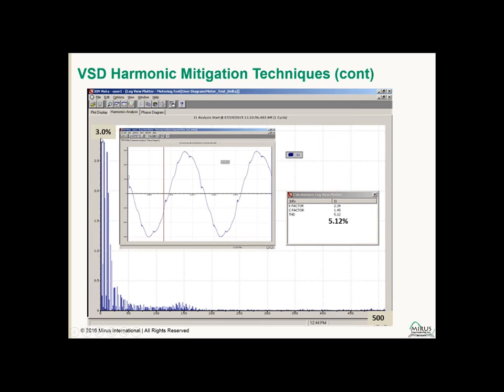And you can see the X scale here is only 3%. So none of the harmonics are higher than the 3% level. And you can see this would be 5th, 7th. There's fairly low levels of harmonics, even in those lower levels, but virtually no higher frequency harmonics, which are what you would get with the active solutions.